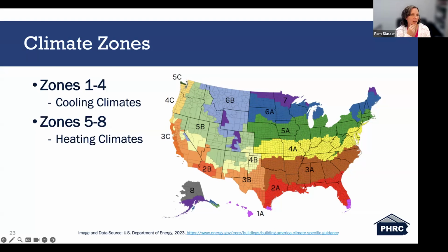If you notice, in Pennsylvania we have two zones in our state: climate zone 4 and climate zone 5. Climate zone 4 falls into the cooling climate zone. However, we all know the southeast corner of the state can get pretty cold in the winter as well. So you still want to keep that in mind when you're planning what type of heat pump system or heating system you're going to put in the home. Understanding the heat pump that you're installing or designing for is going to be very essential. Be sure to check manufacturer specifications to be sure the system will work best in the climate zone that the home is being built in as well.